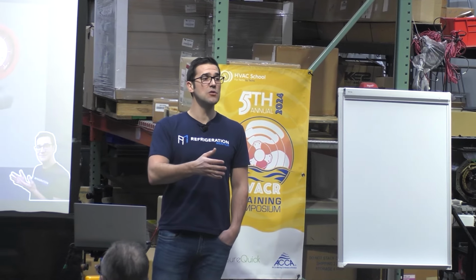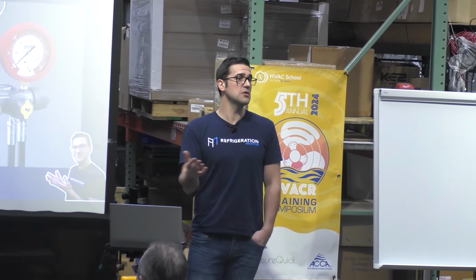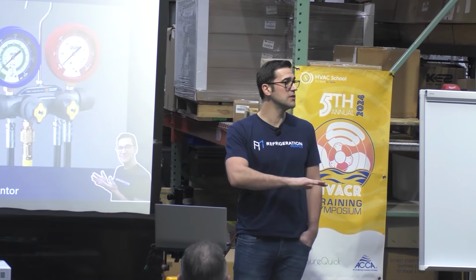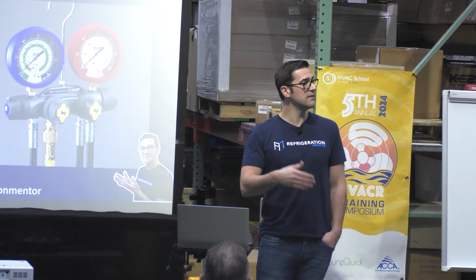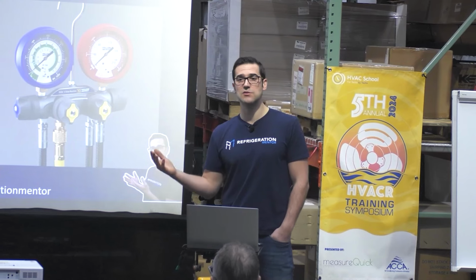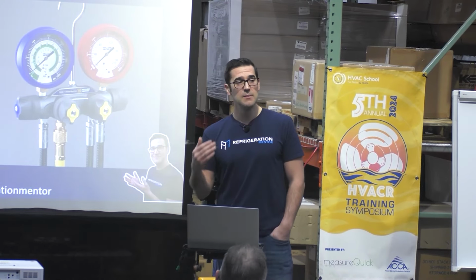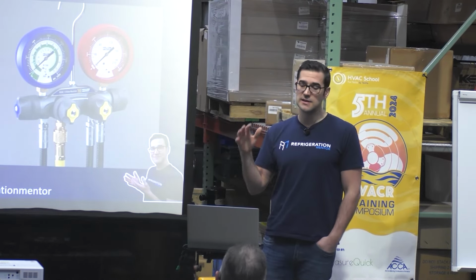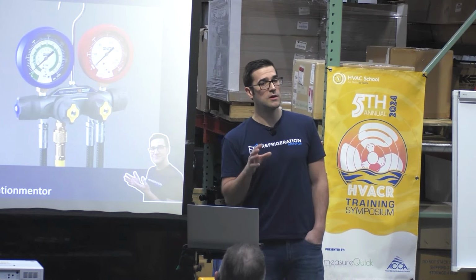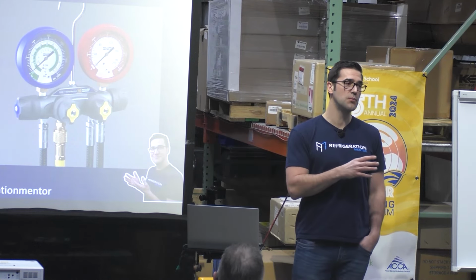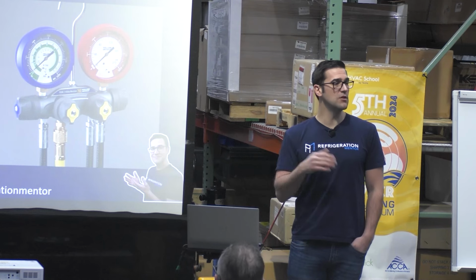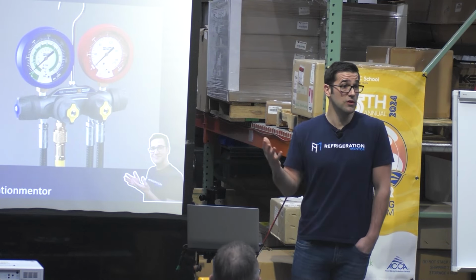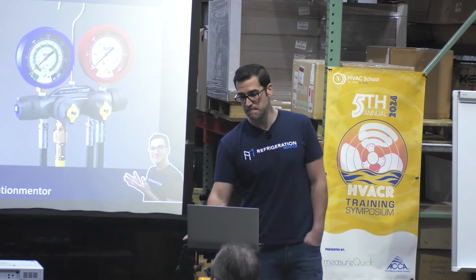Could you use that on the low temp? You could. You could use it on the low temp system because you're running around 200 psi. So those 410 gauges or CO2 subcritical gauges will be able to handle it. But if you're ever working on the high side, you need to have transcritical gauges. One good thing about CO2, there are so many pressure and temperature probes that you don't have to worry about that, because you can use the controller and look at everything. That's what I love about it.